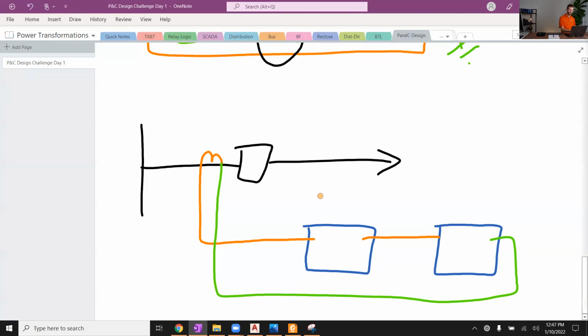Again, always remember your CT polarity dots. And this is the polarity dot side and polarity dot side on the relay as well. So that is called sharing a CT. These 2 relays are in series with one another on the CT secondary circuit. That is another possibility, and we'll show you something like that on an actual 1-line and 3-line drawing later on.